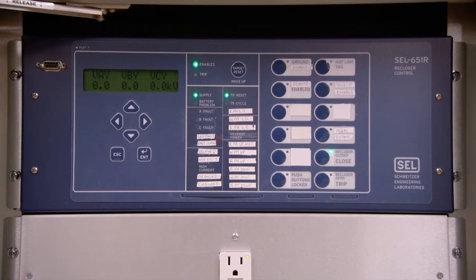You would then be able to safely install the leads up on the main line. Then you would be able to close the bypass switch. When you close the bypass switch, you'll see a portion of the current flowing through the recloser. It will be displayed on the current display, on that scrolling window. Once you see that you have current on all 3 phases, you would then be able to proceed to open the bypass and put the unit into service.